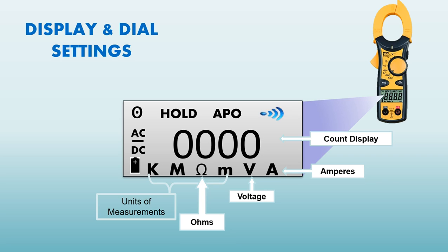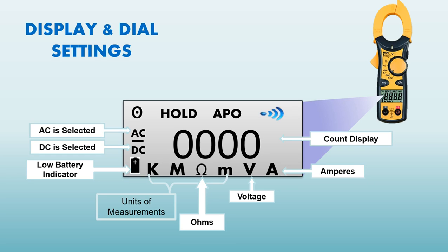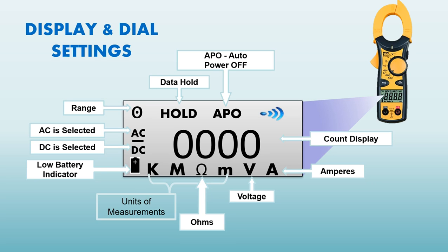This unit has other functions of measurements that we don't actually use in our line of work. These are for use for testing electronics. It also has a low battery indicator. It shows whether you're testing for DC voltage or AC voltage. This is where the range feature shows up. If you press the data hold button, the auto power off will display here, or if you're testing for audible continuity, you will show at this corner.